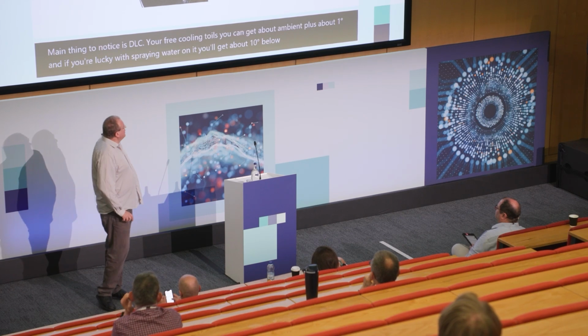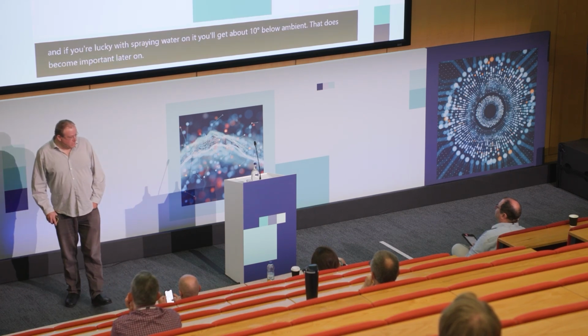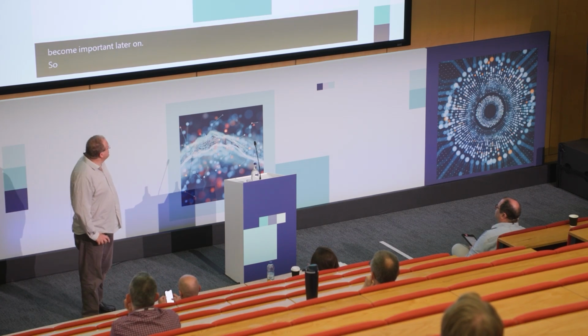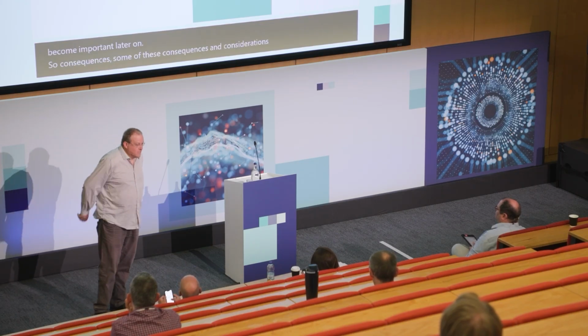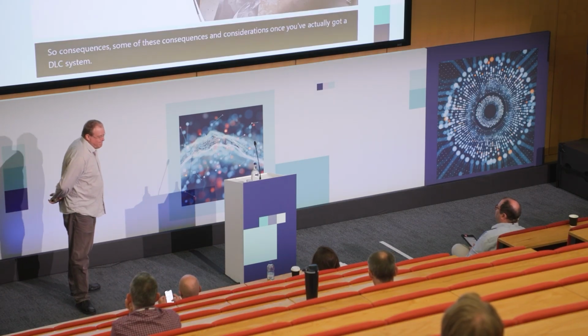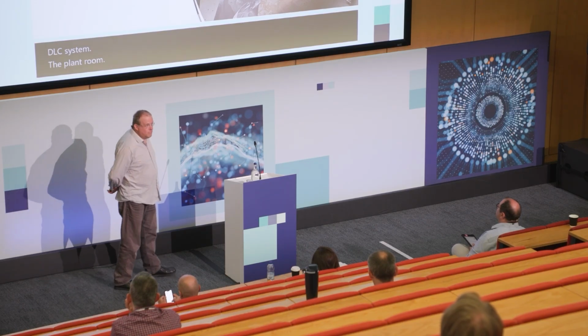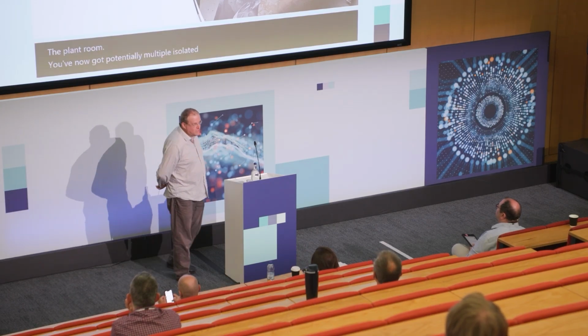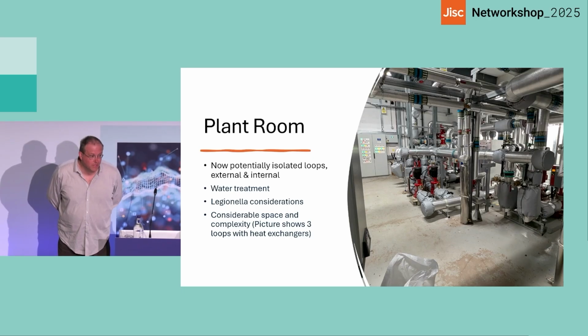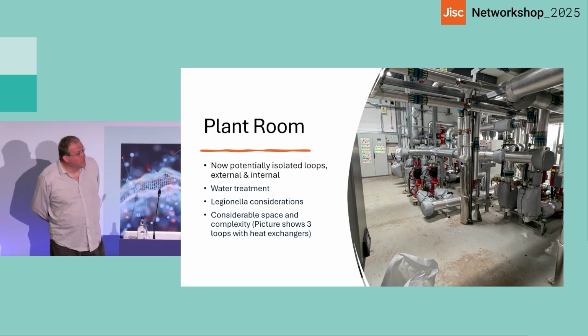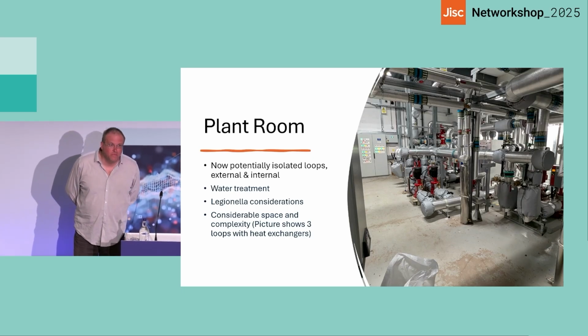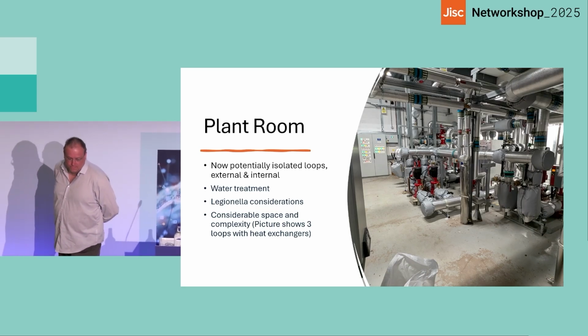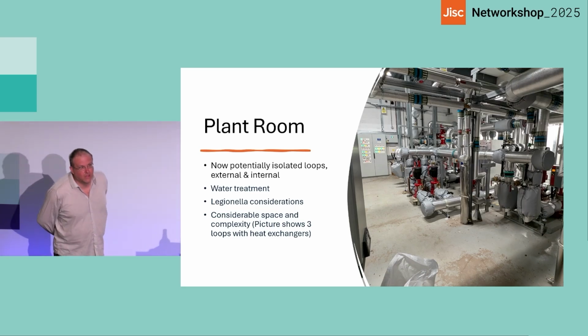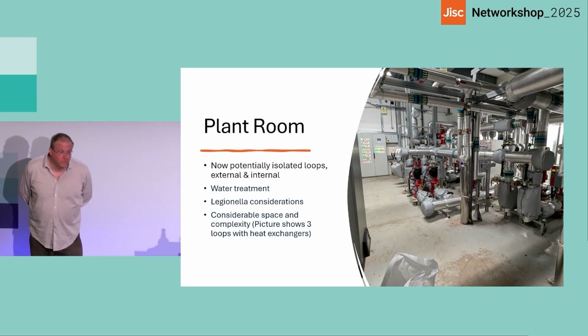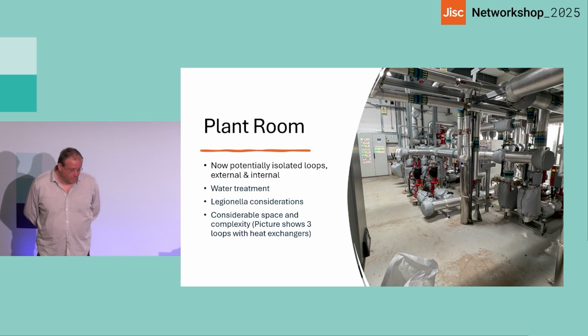That does become important later on. So, consequences. Some of these consequences and considerations once you've actually got a DLC system. Your plant room. You've now got potentially multiple isolated loops because you're going to generally have a different water composition inside from outside. You may have got away with it in the previous examples where you're doing air-cooled with liquid. You'll generally have a loop. In DLC, you'll generally have heat exchangers of some form to isolate the outside loop and the inside loop because they've got different parameters, needed chemical makeups and things.